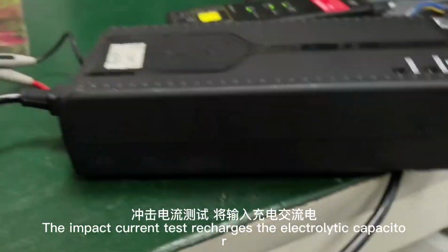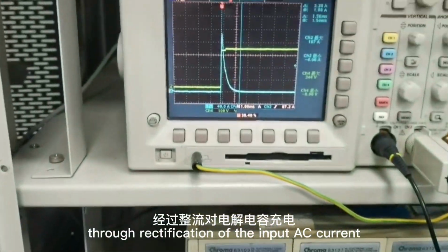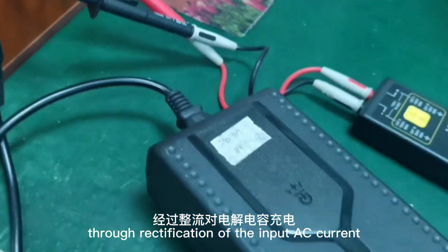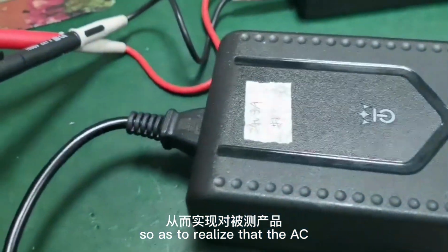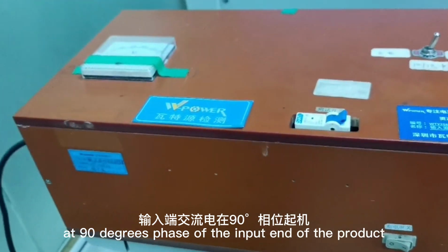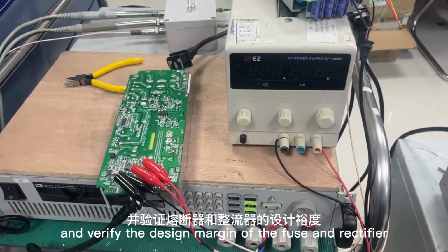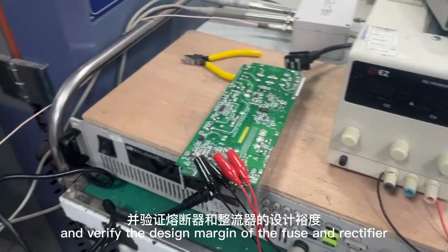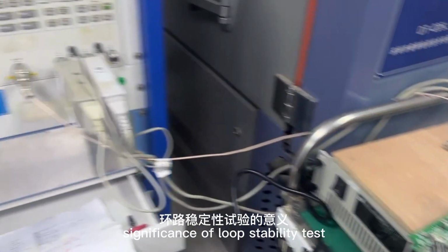Impact current test recharges the electrolytic capacitor through rectification of the input AC current, so as to apply AC at 90 degrees phase at the input end of the product under test, and verify the design margin of the fuse and rectifier. Significance of loop stability test.